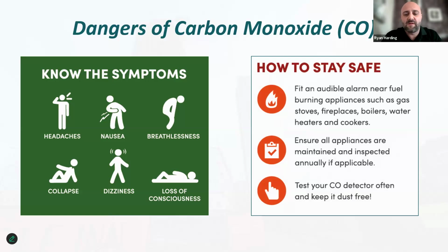So it's important that these devices do have this CO alarm installed nearby, as well as gas boilers, gas water heaters, gas stoves, and so on. Also, it's always worth saying, if the point of exit for the carbon monoxide, i.e. the flue going outside, isn't directly going outside but may go through another room, it is also worth remembering to put a CO alarm in that room just in case that leak happens further down the route to exit.